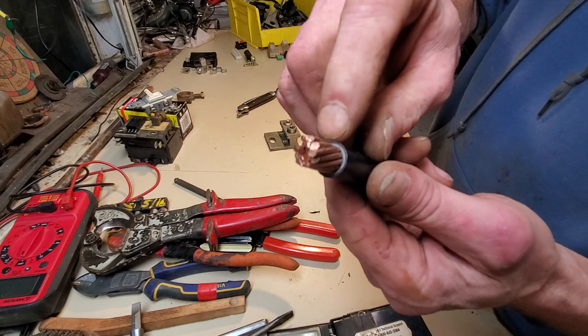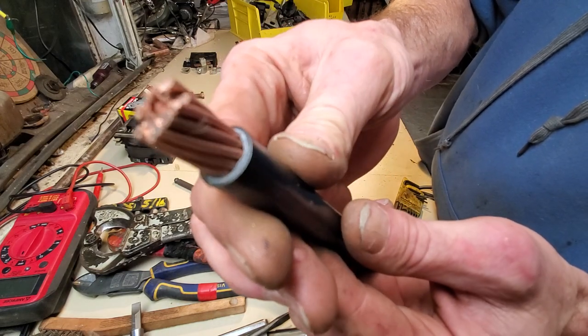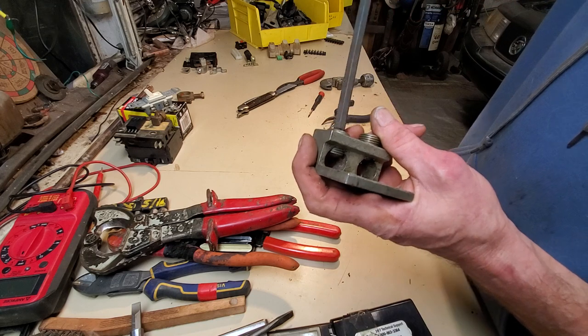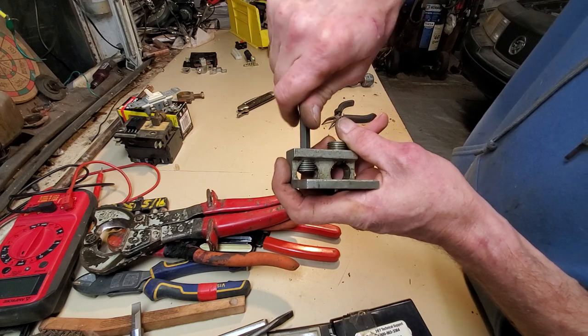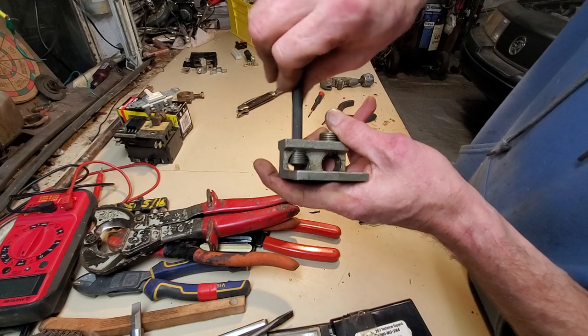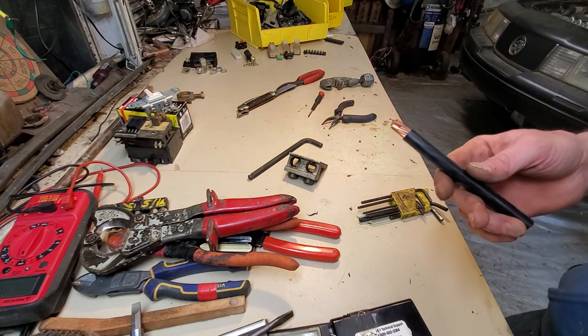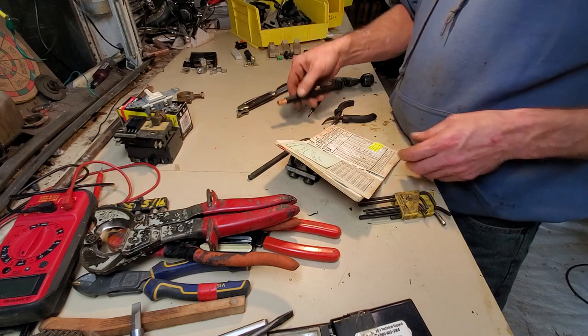This has been cut previously with the pipe cutter — it's in pretty good shape. Here's what I also don't like: what I consider friction-type connections. You put the wire in the hole and tighten an Allen bolt down, and by friction it's held. This connector is engineered for 350 MCM cabling, and 350 MCM is about six sizes bigger than this 2-ought wire.